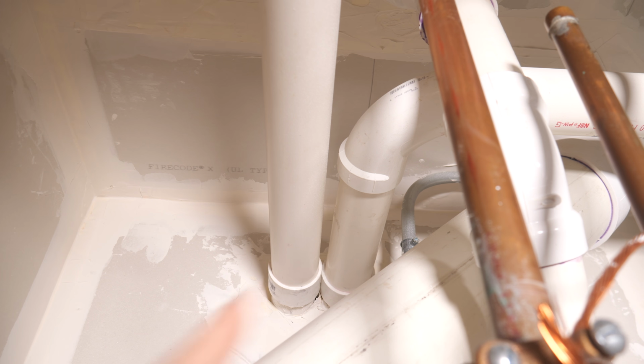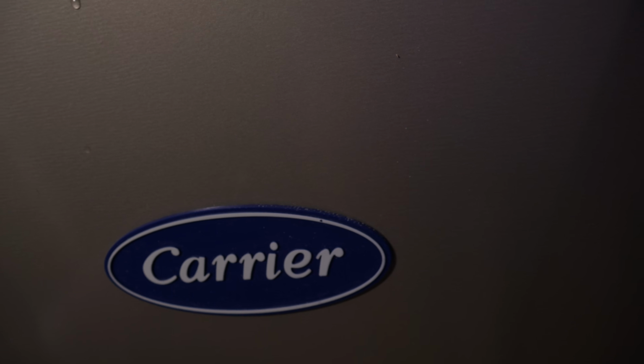Yeah, this pipe here, it goes all the way outside. The point of this is to allow the furnace to have combustion air without creating negative pressure in the building. When this panel is closed up, the combustion section of this furnace is effectively outdoors. It draws in fresh air through here, which brings in enough oxygen to set some methane on fire, and then pushes the exhaust gases out this other pipe.